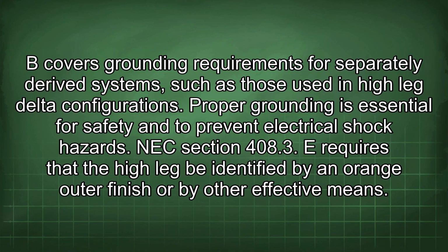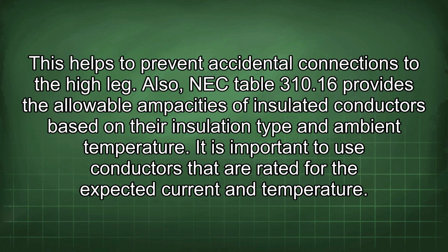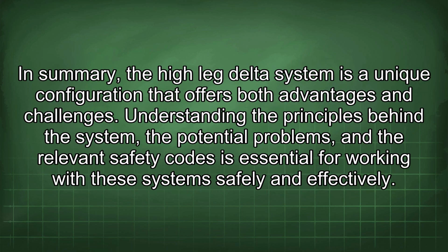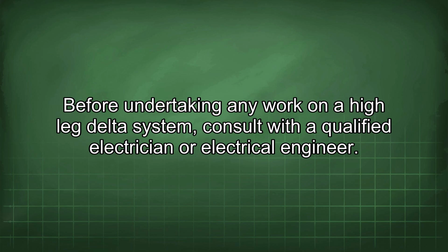NEC Section 408.3 requires that the high leg be identified by an orange outer finish or by other effective means. This helps to prevent accidental connections to the high leg. Also, NEC Table 310.16 provides the allowable ampacities of insulated conductors based on their insulation type and ambient temperature. It is important to use conductors that are rated for the expected current and temperature. In summary, the high-leg delta system is a unique configuration that offers both advantages and challenges. Understanding the principles behind the system, the potential problems, and the relevant safety codes is essential for working with these systems safely and effectively. Before undertaking any work on a high-leg delta system, consult with a qualified electrician or electrical engineer.